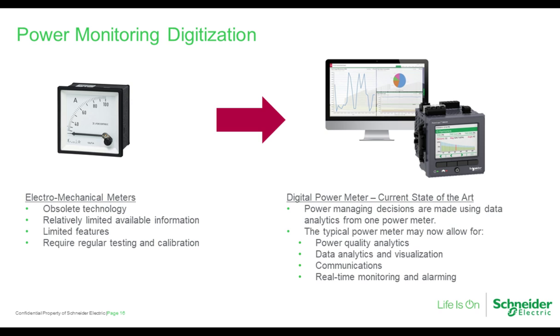One of the other things is power monitoring and digitizing power monitoring. As we walk through some older facilities, we can see that there are old digital or old analog meters out there, in all kinds of places, that were put in many, many years ago. And those really don't give you a good idea of what's going on in the system. They can only tell you that you've got voltage and amps. They're very limited in the information available, limited in features, and require regular testing and calibration. And we've seen these meters out there all the way down to electromechanical watt-hour meters.